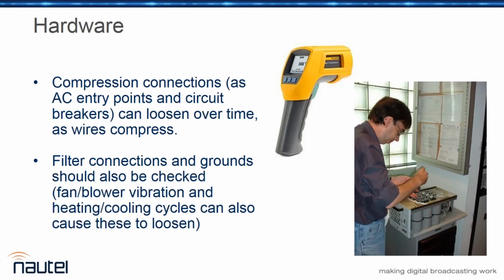Again, beating the drum on compression connections: make sure they're tight. I don't know how old that picture is, but it's more than 5 or 10 years old. Here I'm working on an ND10 power module, tightening the terminal block connections on the bottom of a power amplifier. Any kind of connection, once a year, go through and check power supplies, circuit breaker connections, filter connections, grounds, everything. All of that should be tightened on a schedule.